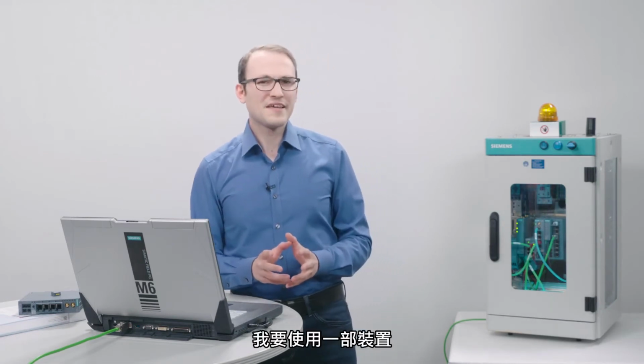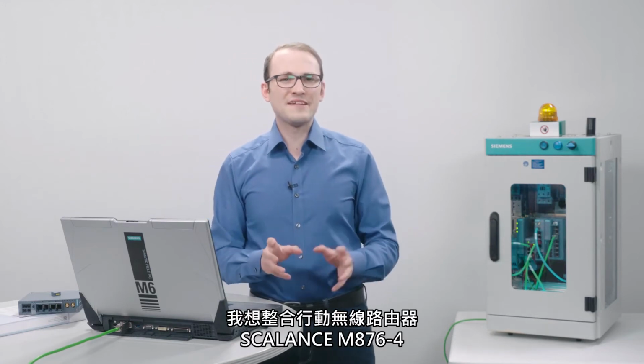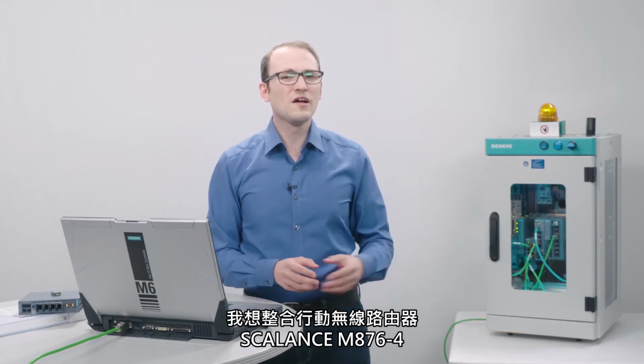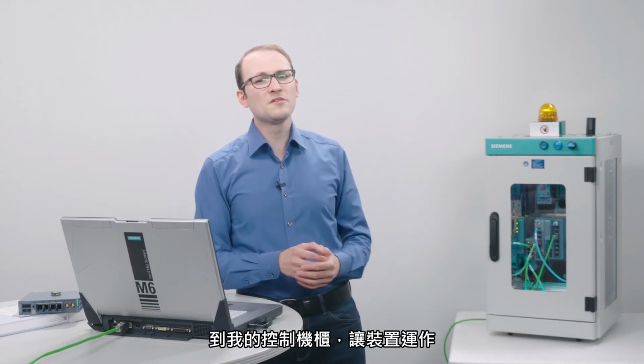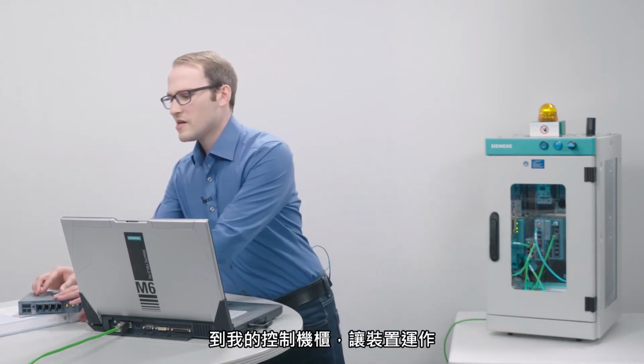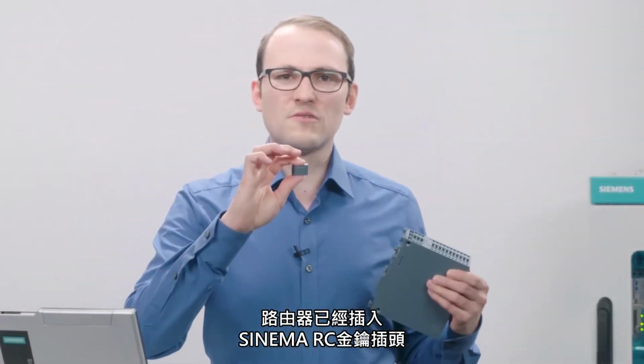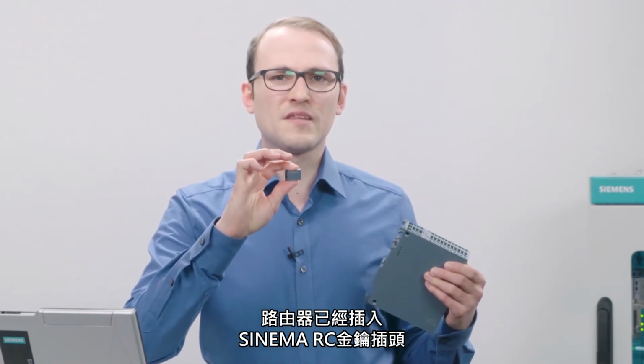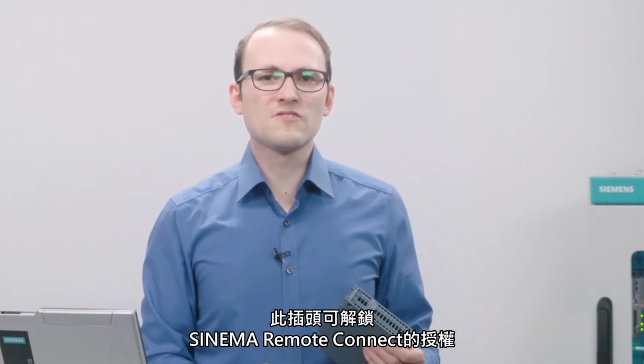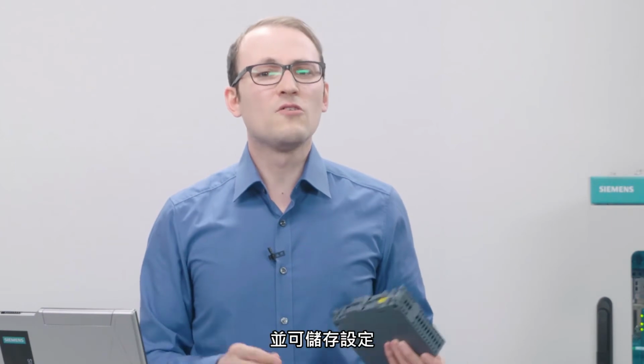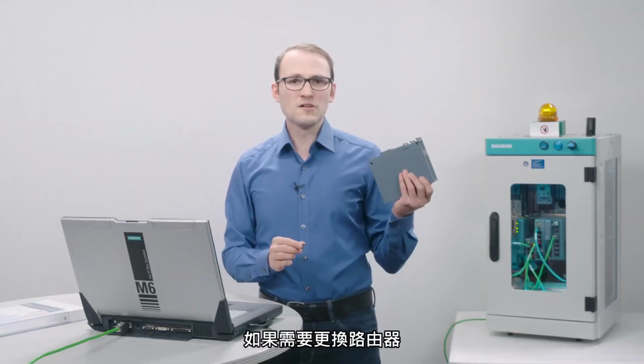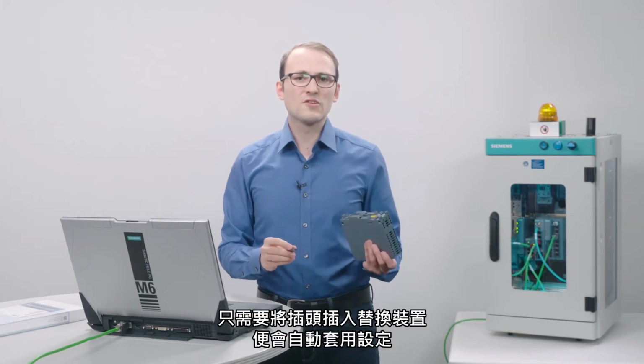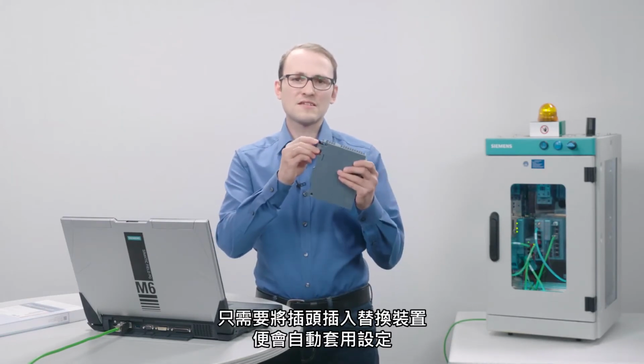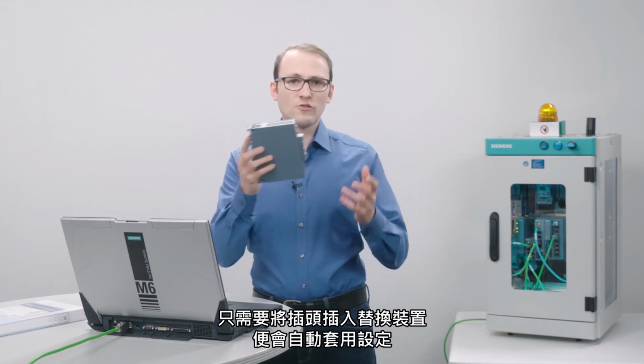I'll start with a device. I want to integrate the mobile wireless router Scalance M876-4 for my control cabinet and put it into operation. A SINEMA RC key plug is already plugged in the router. The plug unlocks the license for SINEMA Remote Connect and also stores the configuration. If the router needs to be replaced, the plug is simply plugged into the replacement device and the configuration is automatically applied.